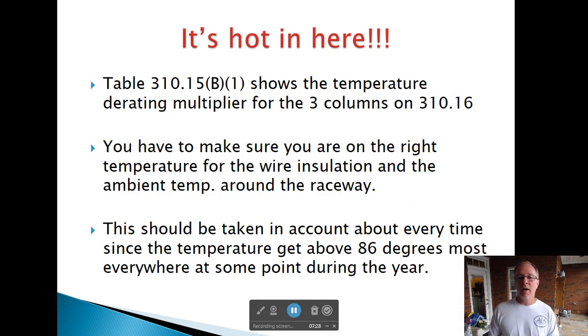Table 310-15-B1 shows the temperature de-rating multiplier for the three columns on 310-16. And that's the kicker there. A lot of guys get tripped up because they look at the three columns on this table and think, which one do I need? Well, it's based on your insulation type. If you look on Table 310-16, there are three columns—your TW, THW, and THHN, or your 60, 75, 90. This table has the same columns. So if we use the 90 degree column on Table 310-16, we need to use the 90 degree column on Table 310-15-B1. You have to make sure you're on the right temperature for the wire insulation and the ambient temperature around the raceway.